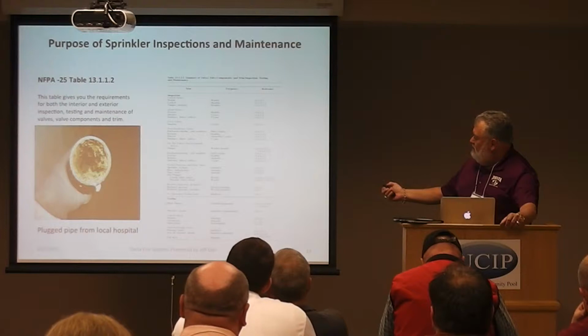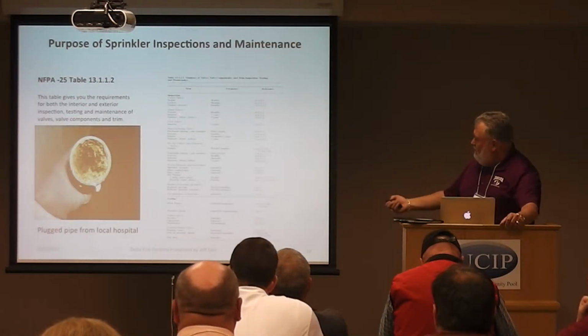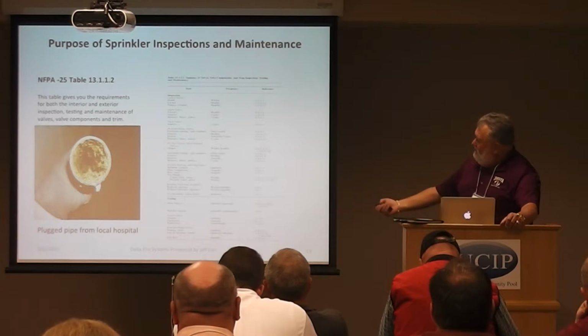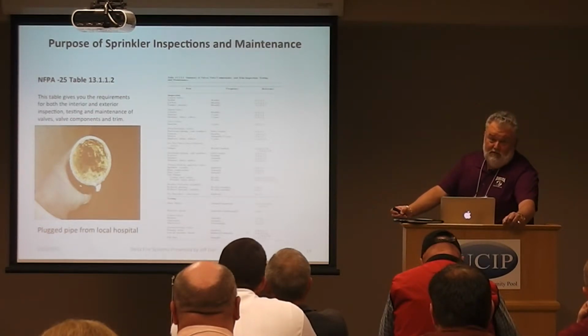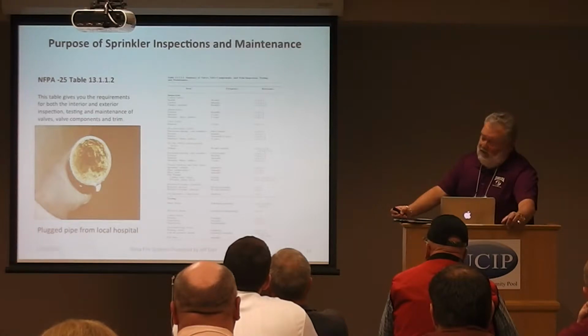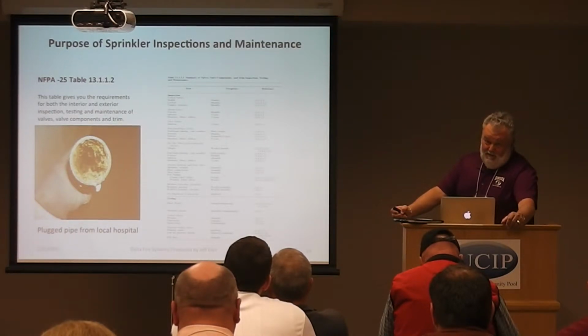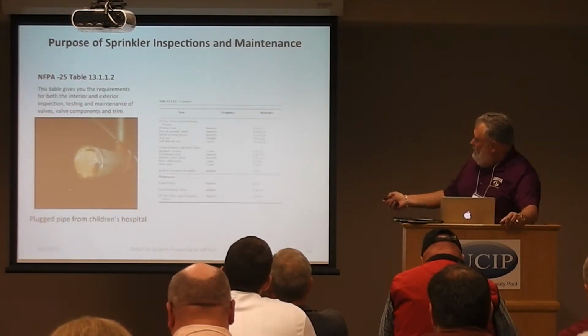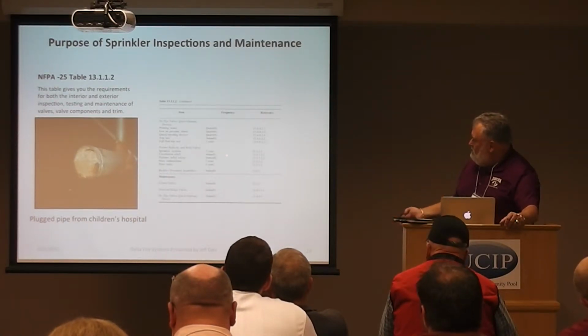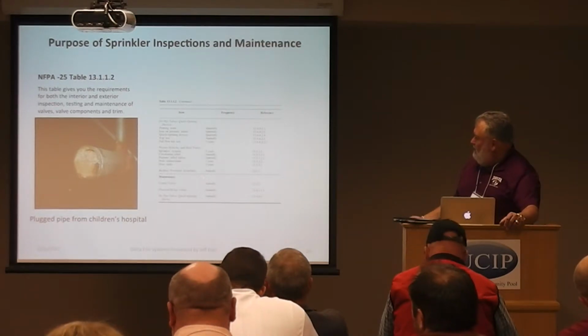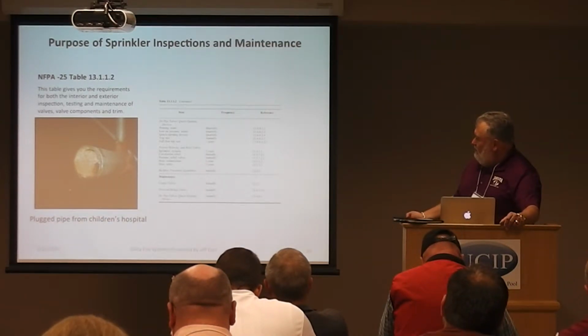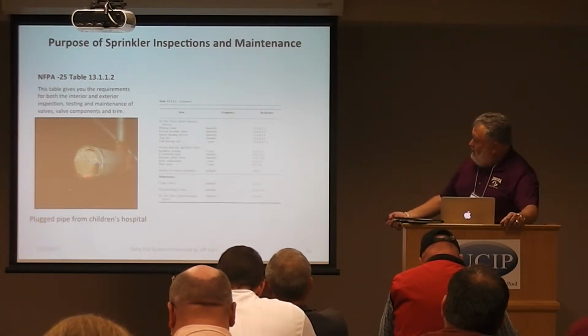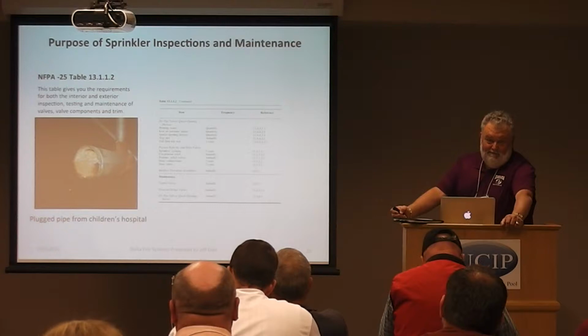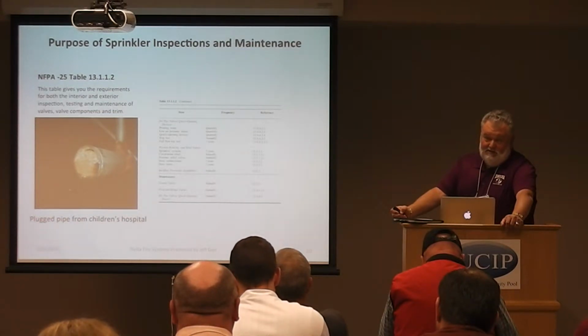Here again, the same area is broken down. Here's what's required for inspections. Here's testing. Look at that pipe right there, which was pulled out of a local hospital here. I won't mention which hospital, but obviously if you think that system would work, I wouldn't feel safe being in that hospital myself. Here's the maintenance part of what's required right here. Tells you annually, quarterly, 3 years, 5 years. Again, that pipe right there came out of a local children's hospital. So if my child was in the hospital, I want to make sure.